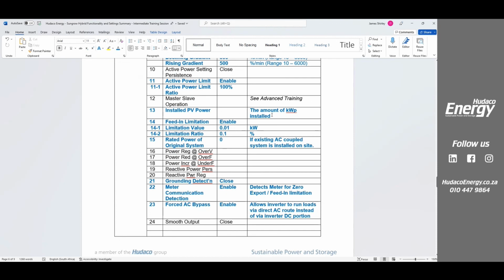Install PV power, this you would have to set every single time. The feed-in limitation, we set this during the initial configuration, but you can go in and change this anytime. It's a setting. So if, for example, suddenly the site gets registered and everyone's happy for you to feed in, you just come here and instead of enable, you would just close the feed-in limitation, and then it would start exporting back to grid. Or, like in Australia, for example, they say, well, you can feed in, but you can only feed in 3 kilowatts. Okay, no problem. We can then just put 3 kilowatts here instead of 0.